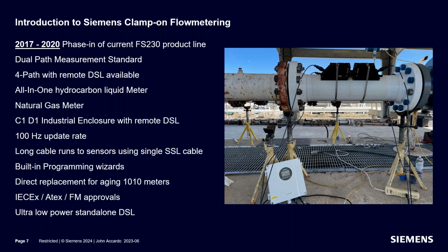A 4-path with a remote DSL was available, and an all-in-one hydrocarbon liquid meter, a natural gas meter, a class 1 div 1 enclosure with remote DSLs. It brought a 100 hertz update rate and long cable runs, much longer than we were able to do with the previous generation systems. That was made possible through the use of an SSL cable to the remote DSL, so that the actual transducer cables can be very short, and then all the data gets transferred over an Ethernet cable back to the transmitter, which is much more noise immune and is capable of much longer cable runs.